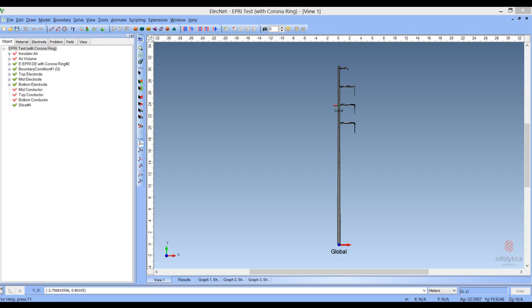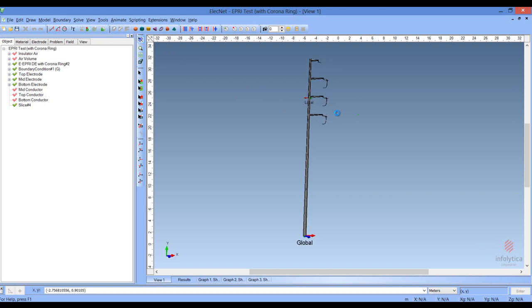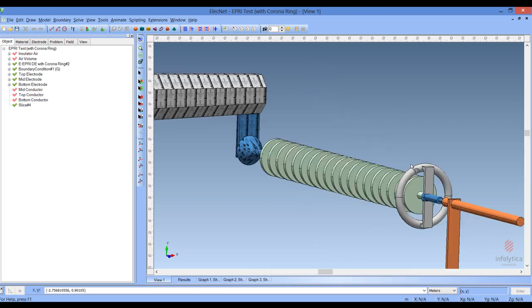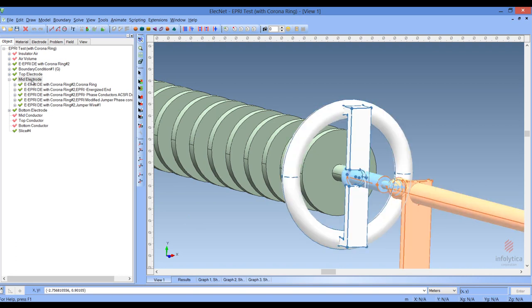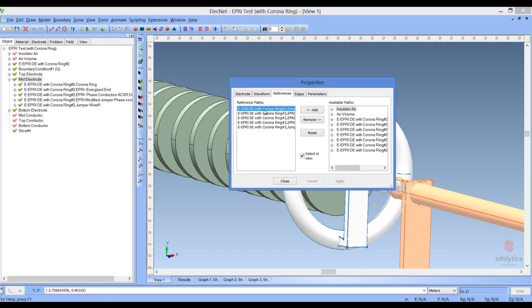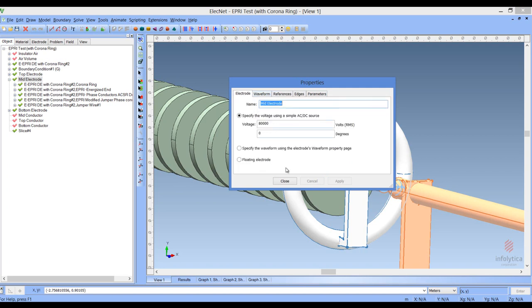For the final part of this analysis of the suspension system, we will look at the new model with the corona rings attached to the energized end of the string. I have loaded this model. We will zoom into the area of interest and rotate the view for better viewing. Now we can see a good view of the end. The mid-electrode is composed of the corona ring, the energized string, and of course the phase wires for that phase. Looking at the properties, the electrode has 80,000 volts applied to it.